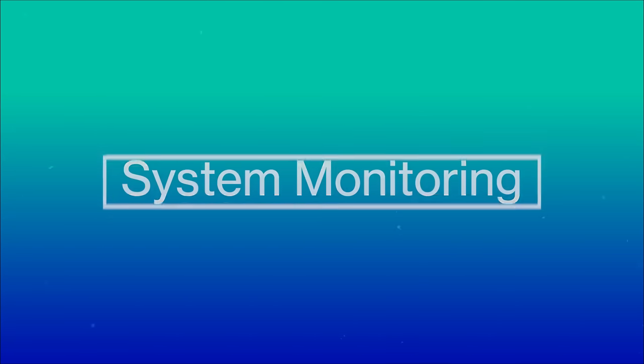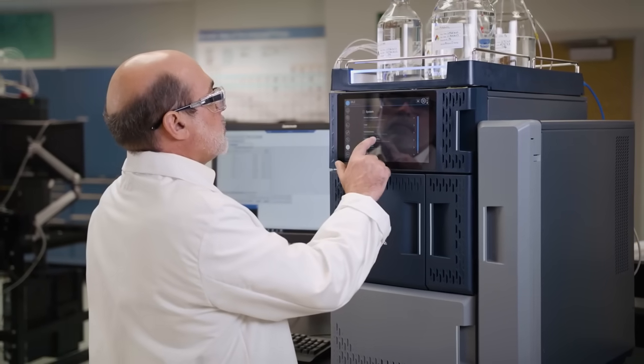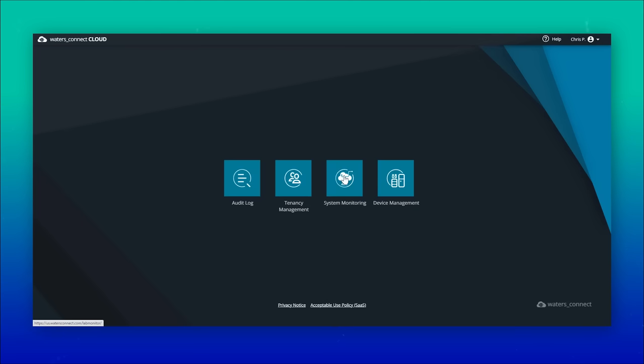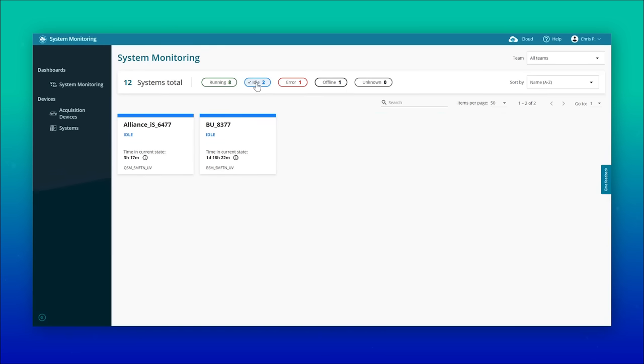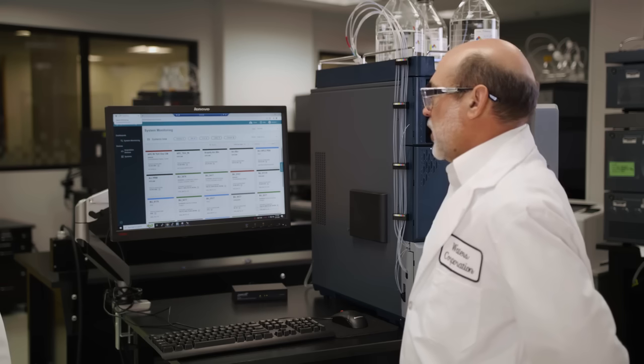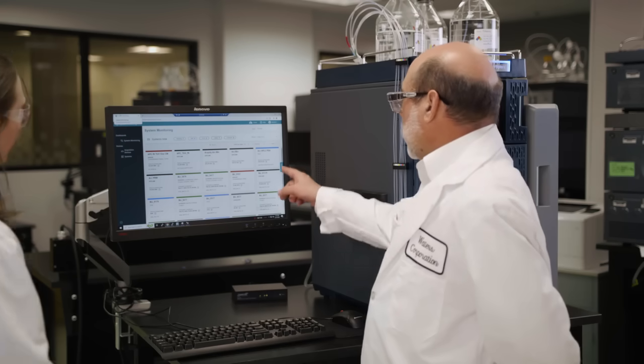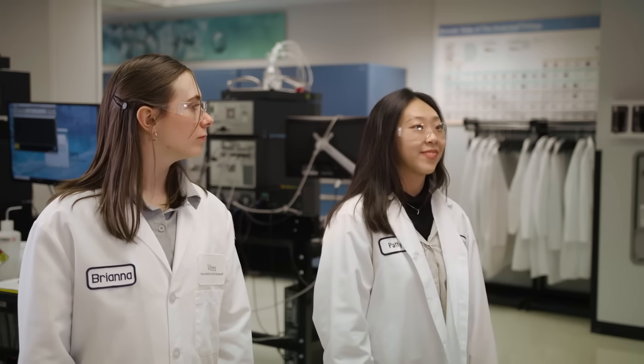The Alliance HPLC system delivers clear feedback on the system through a number of means. It integrates with the Waters Connect system monitoring software, which provides a fast visual diagnostic assessment on the system status beyond what is observable for any other chromatography system, as well as the status of any other Empower software controlled chromatography systems. You can access this information anytime from anywhere.